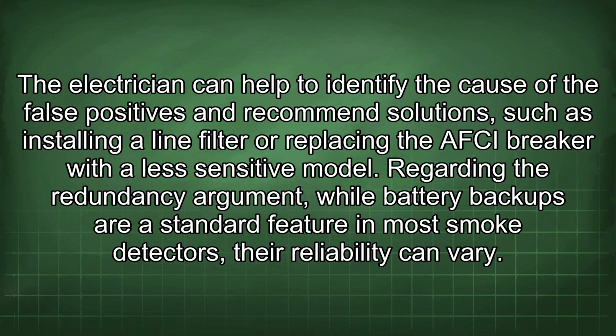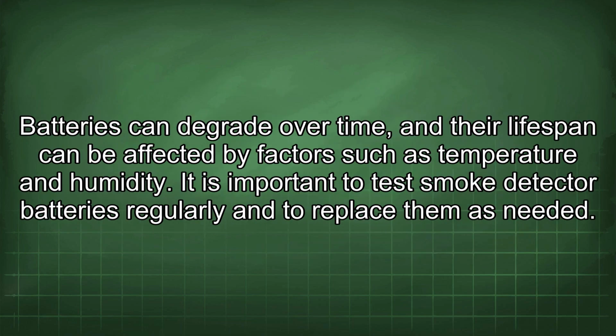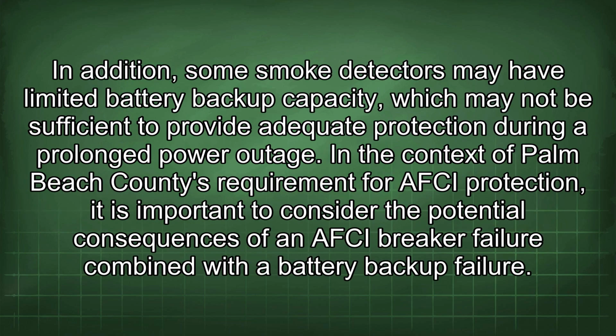Regarding the redundancy argument, while battery backups are a standard feature in most smoke detectors, their reliability can vary. Batteries can degrade over time, and their lifespan can be affected by factors such as temperature and humidity. It is important to test smoke detector batteries regularly and to replace them as needed. In addition, some smoke detectors may have limited battery backup capacity, which may not be sufficient to provide adequate protection during a prolonged power outage.